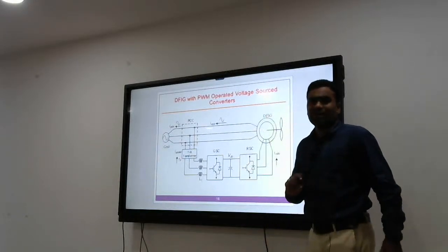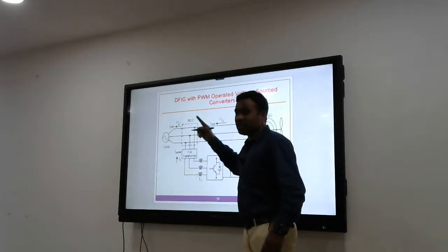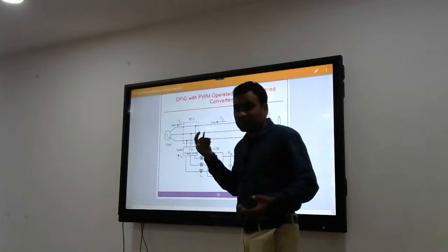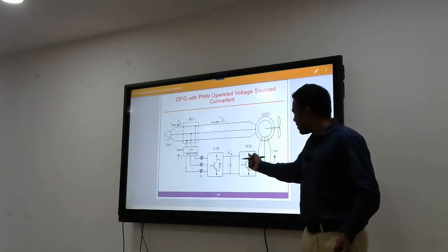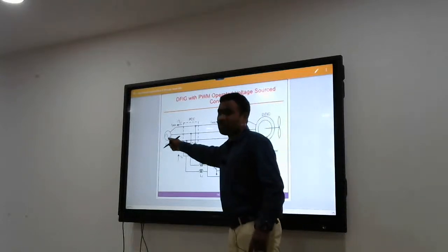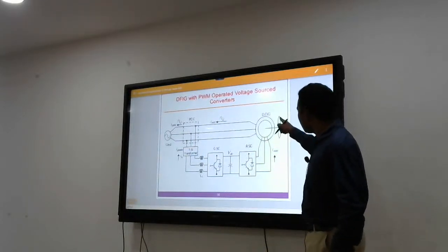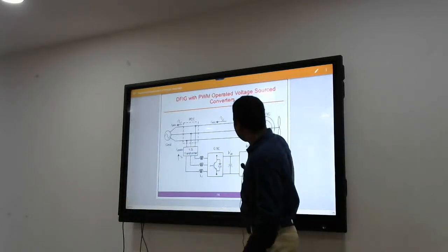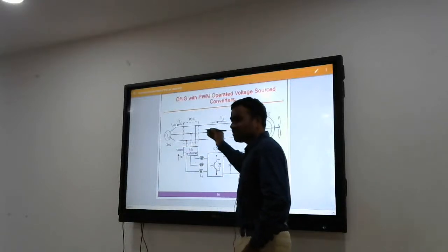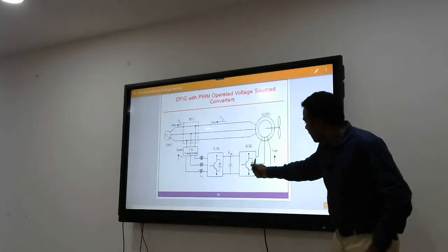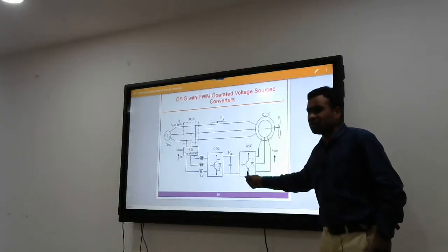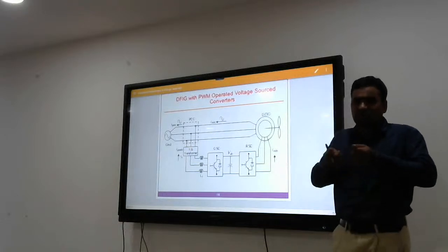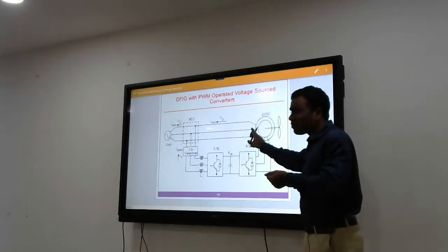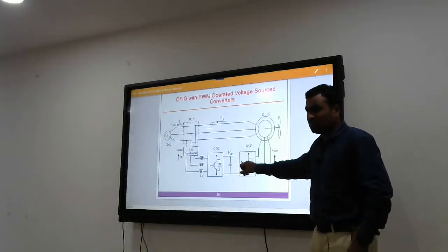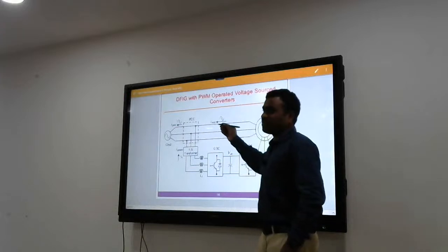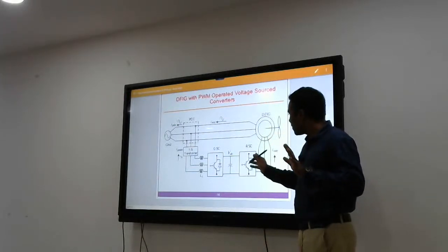One more thing, the stator is directly connected to the grid, so where will I get the reactive power for this DFIG? Suppose you are not giving it from anywhere, it will draw the reactive power from the grid. It will take the reactive power from the grid and mechanical power will be converted into electrical active power. Active power will be in this direction and reactive power will be coming from this direction. But if you start providing the reactive power using this rotor side converter, you are injecting the reactive power into the rotor circuit, then your machine is getting the required reactive power from this converter, so it won't draw any reactive power from the grid. Suppose you are not giving any reactive power from the rotor, then it will draw completely.